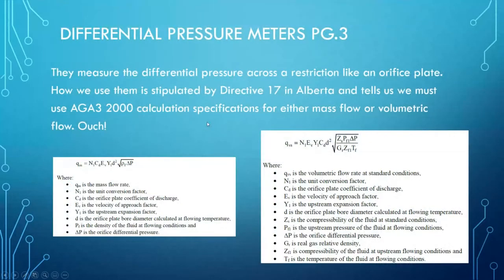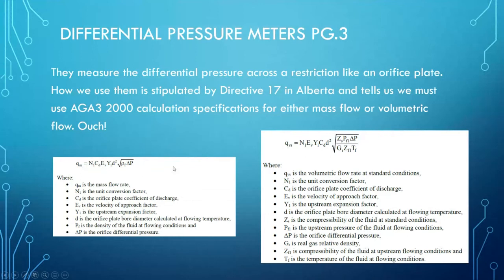Differential pressure meters measure the differential pressure across a restriction like an orifice plate. Directive 17 in Alberta stipulates we must use AGA 3 year 2000 calculations for either mass flow or volumetric flow. There are elaborate calculations involved. The key difference between calculating mass flow rate for a liquid versus volumetric flow at standard conditions for a gas is the variable Z, which relates to compressibility.